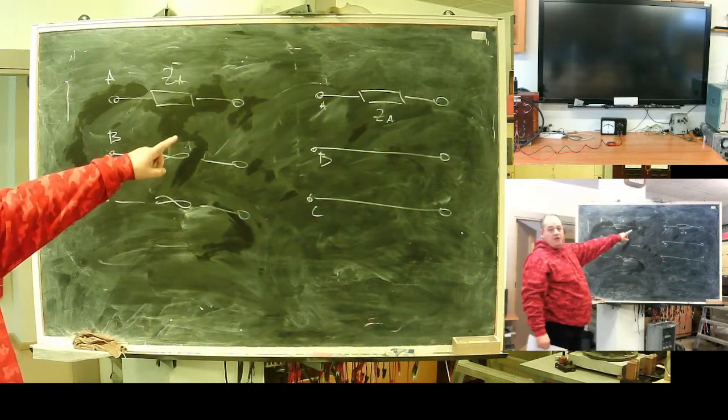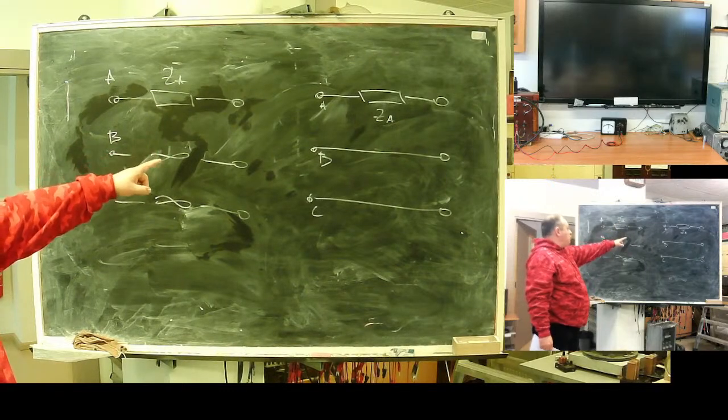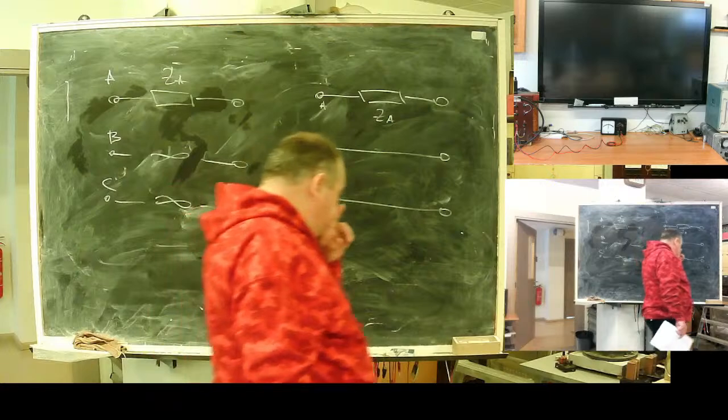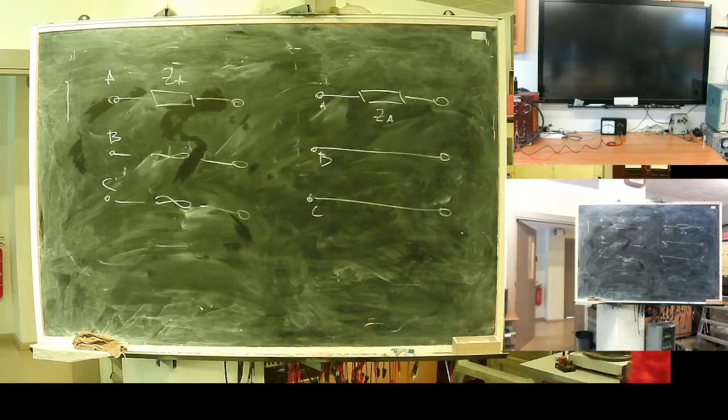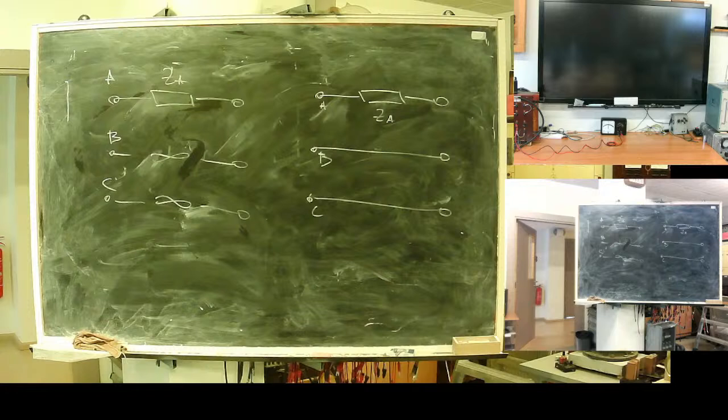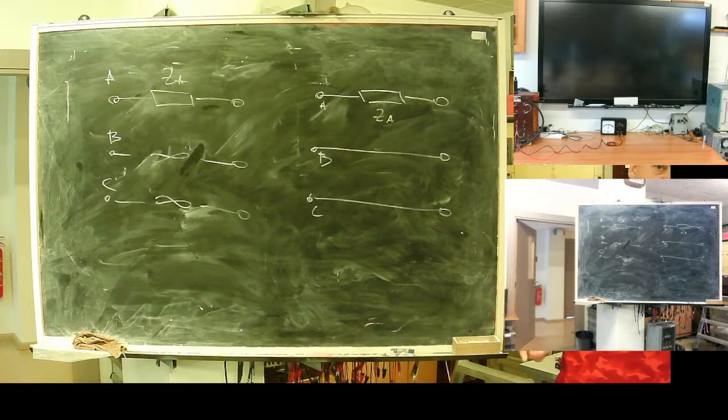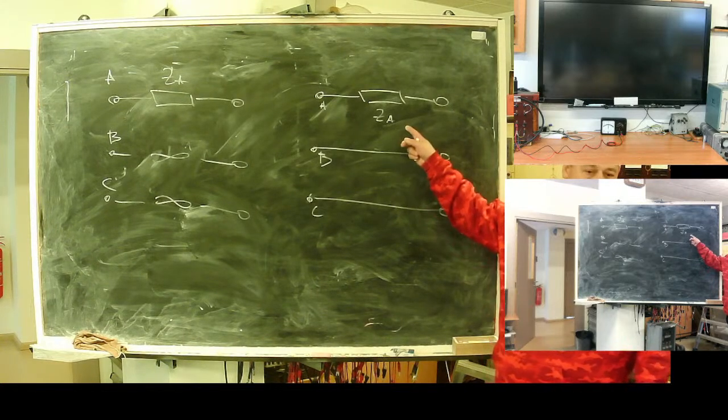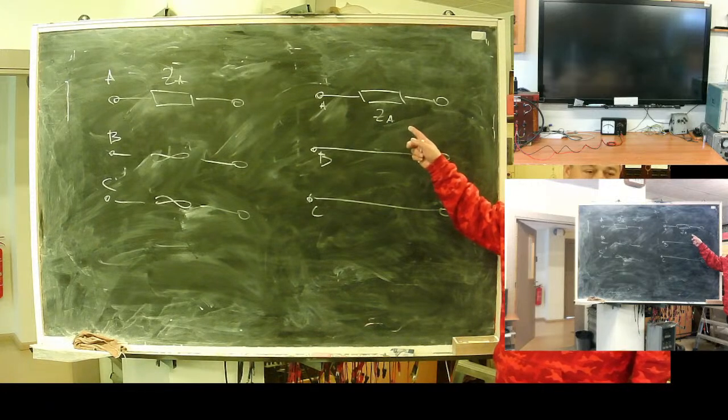It can be up to infinity. One phase interruption is quite an unpleasant thing. Sometimes you need to perform a technical expertise on faulted equipment. And one of the things is badly performed assembly or rust somewhere, when one of the terminals burns out. Normal, one black, rust and burn.